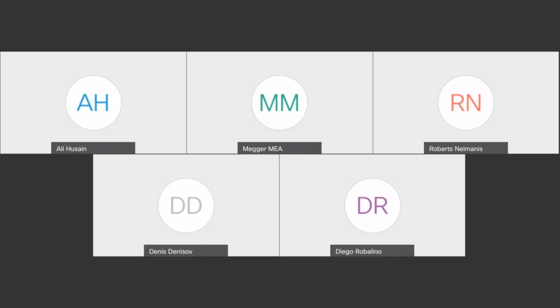The other issue is that most recently you may have seen the C2 value on the nameplate. For the older bushings, you may not find the nameplate for C2, power factor, or capacitance because it may change. Like we were mentioning yesterday, you have 3 bushings similar by construction and installation mounted on your transformer. The ideal is to do a comparative analysis between all of them, and most probably you will have a similar value for all the C2. I wouldn't say that a 2 times or a 200% is critical or not.